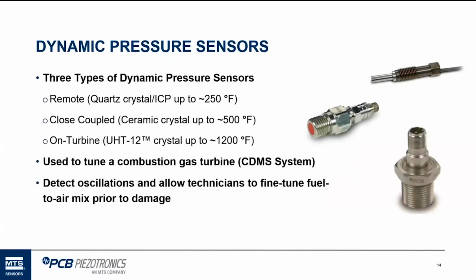So in our range of dynamic pressure sensors, there's not just our range, but everybody's range, there are 3 different types. We've got what we call a remote sensor. That's typically mounted way far away from any extreme heat and can handle only 250 degrees Fahrenheit. It's an ICP style sensor with a voltage output. All the electronics are built into it, and it's usually mounted on a long tube. They call it an infinitube within a case or enclosure, and it's looking at dynamic pressure oscillations via that method.